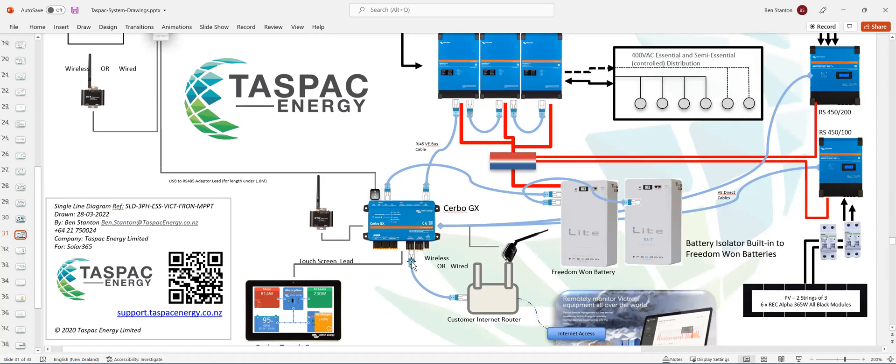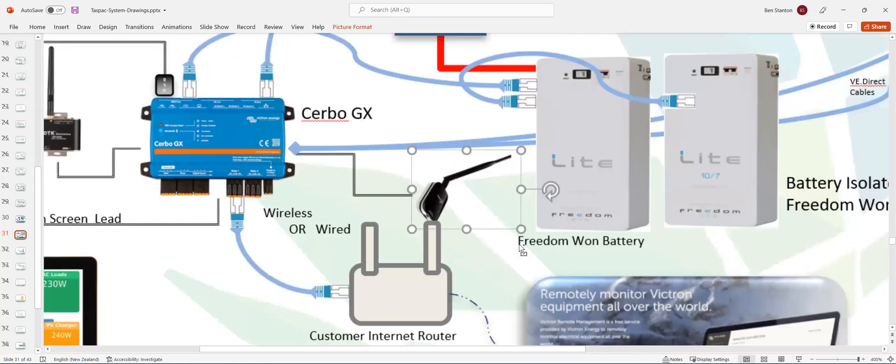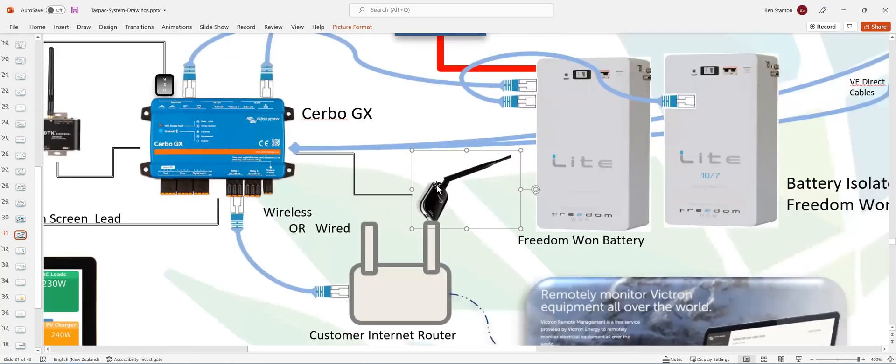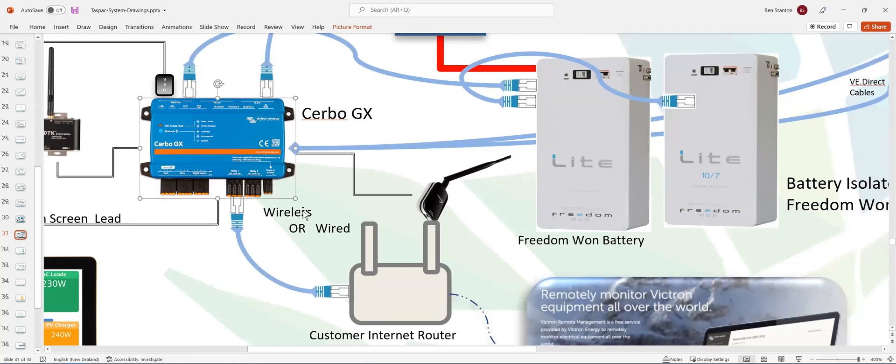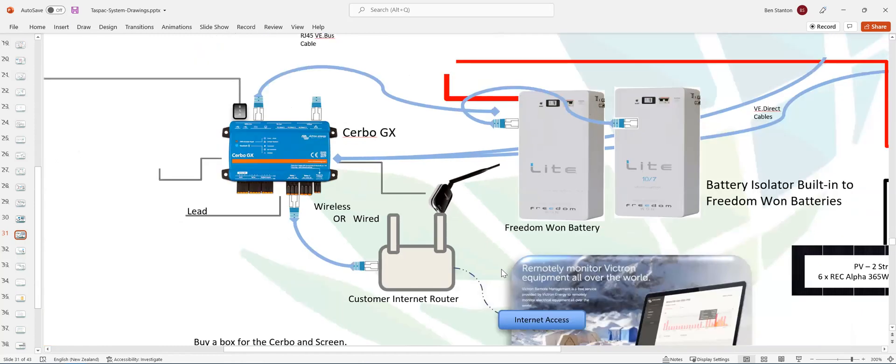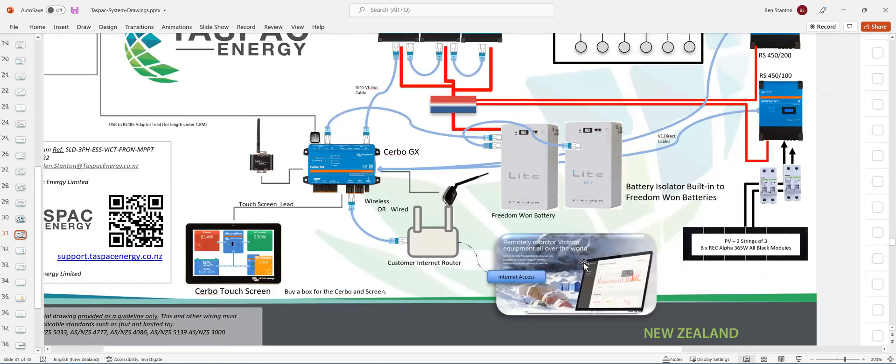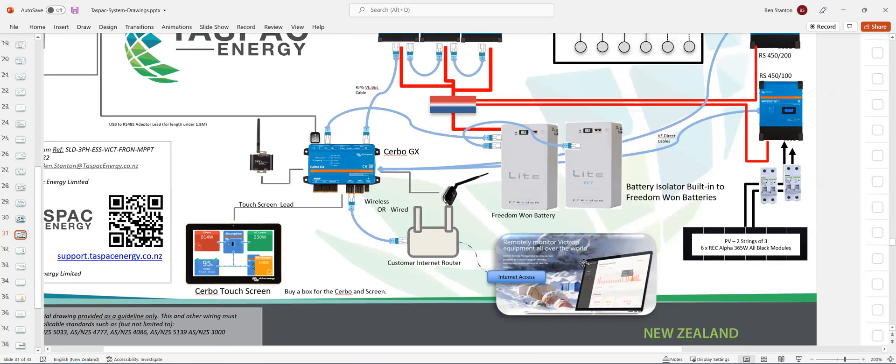Now, the Cerbo GX then connects to the Ethernet router, which is the customer's Ethernet router. That can either be hardwired. If you can get a cable, that's great because it's quicker, more reliable. It reconnects faster, all of that good stuff. But if you can't get a cable to it, then you can connect the wireless, what we call a Gembird. It's just a USB Wi-Fi unit. Plugs into the USB in the Cerbo GX. And then you register it onto the Wi-Fi network of the customer. And away you go. And then you can connect the system to the VRM portal.